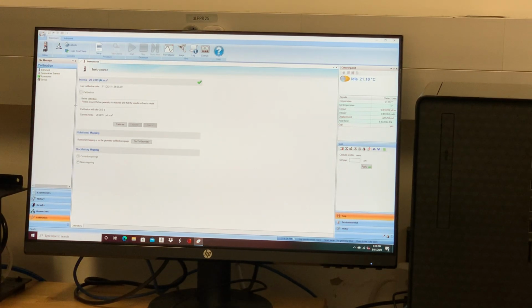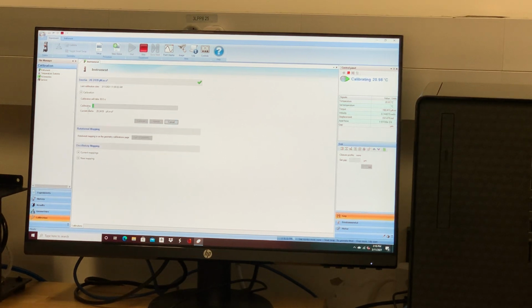But calibration, instrument inertia calibration, I think under that help file it says it needs to be done at least once every 3 months. I typically tell you guys to do it once a month, or if you use the instrument only once every couple weeks, you might as well run it. It's very easy to do. You come here and you hit calibrate. It gives you a status bar and it takes 30 seconds. Okay?